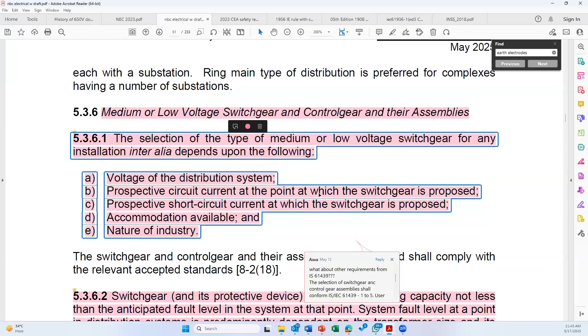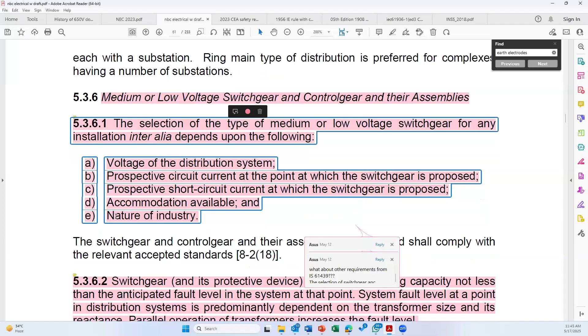The selection of the type of medium and low voltage switchgear for any installation depends, inter alia, on: the voltage of the distribution system, the prospective short circuit current at the point where the switchgear is proposed, the accommodation available, and the nature of the industry. So there are about five explanations given in this case.